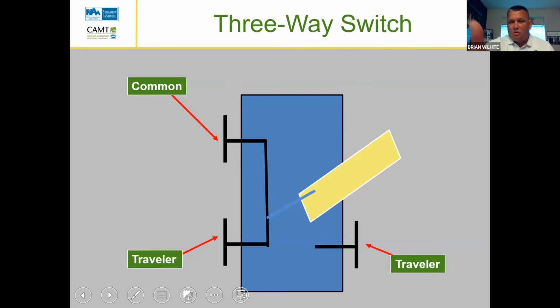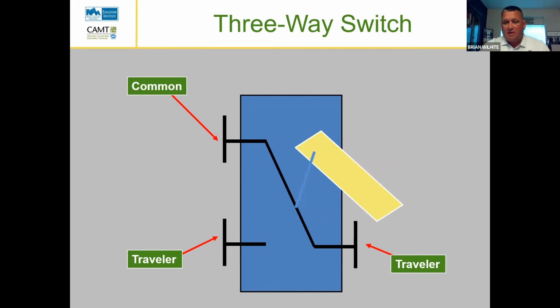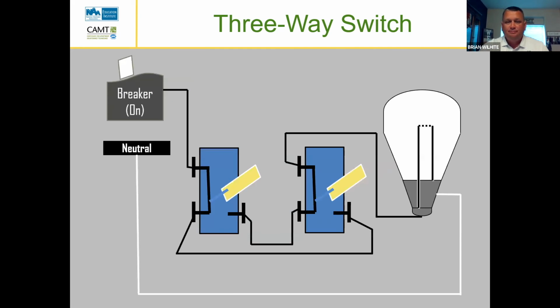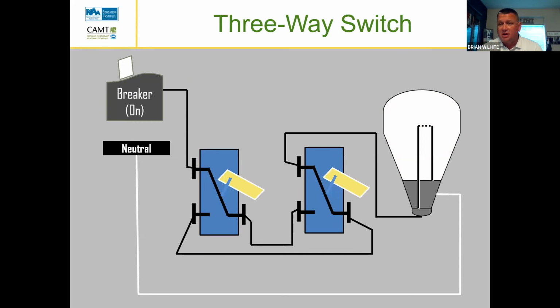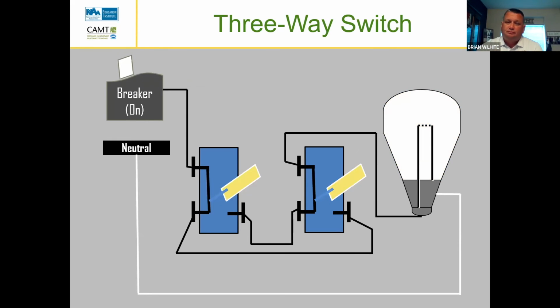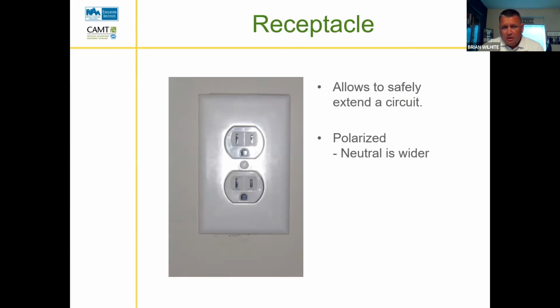And then basically the way it works, if we look at it here, we've got our common, which is our power coming in, and we're just transferring it from one traveler to the next to send power to our light or not to our light. In this case, this is how it would hook up. We'll review this slide again when I come and see you here in December so that we can learn to wire them there. But if you look here, when we make a switch, we turn the light on. We shut the other switch off, it turns the light off. Any questions on three-way switches?